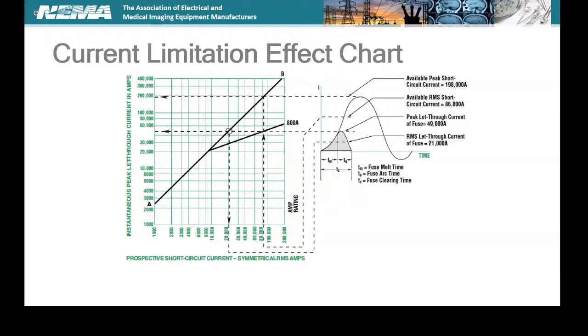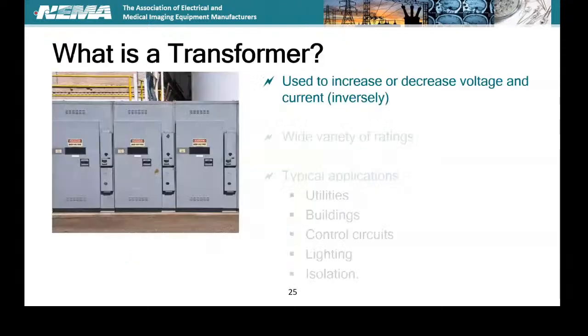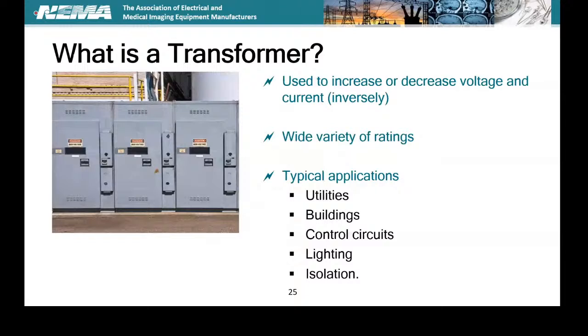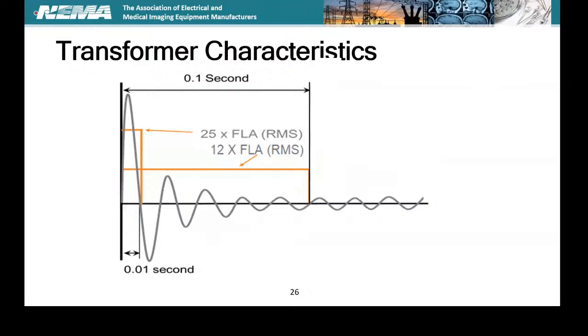Wonderful. Okay, so let's go to transformers. So we all know what a transformer is, variety of ratings, where we use them all, but how do we protect it? So this is your transformer current characteristic, and you see that high inrush current when you're energizing that transformer. And then of course you balance out to a full load ampere, and you see a short time duration where you get that high inrush. And what we're going to do is look at what are the fuses that we want to look at for transformers.